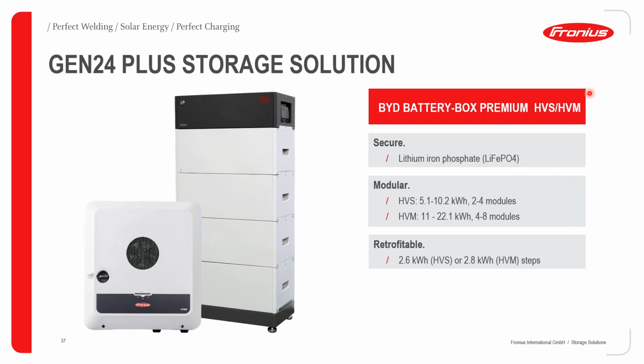So when you're talking about the HVS series, you can start with 2 up to 4 modules. You can see this battery stack here, it has about 1, 2, 3, 4 modules. And then you get a maximum of about 10.2 kilowatt hours for the HVS series. When you look at the HVM, you can have 4 to 8 modules, and therefore you can get a maximum of 22.1 kilowatt hours per battery stack.